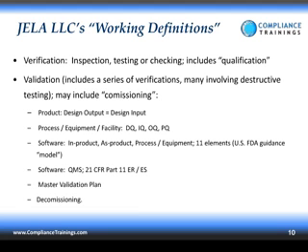Now you notice one of those sub-bullet points, process equipment facility, DQ, IQ, OQ, PQ. Those are qualifications: design qualification, installation qualification, operation qualification, performance qualification. So to me, in this case, qualification, as far as my working definition, is synonymous with verification.